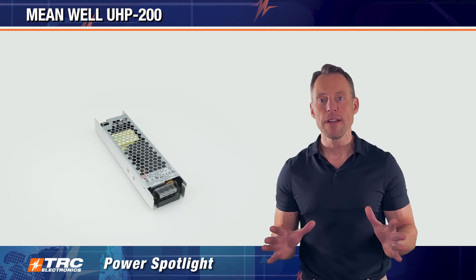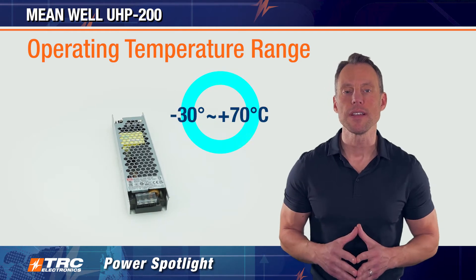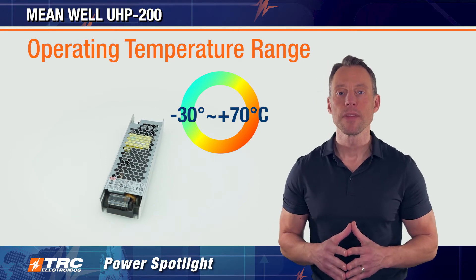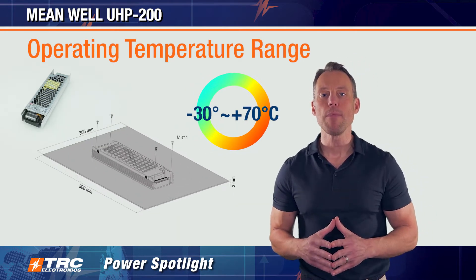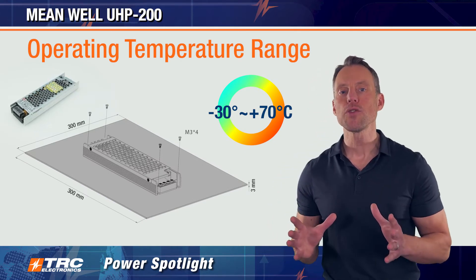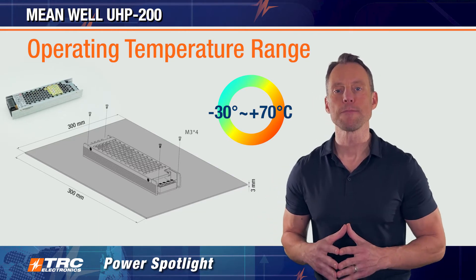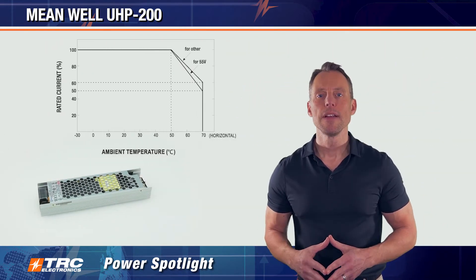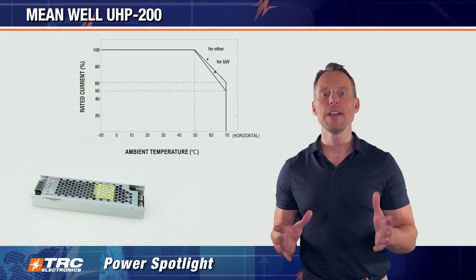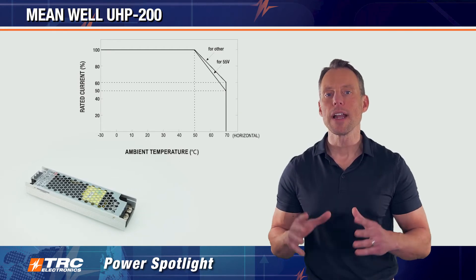This power supply has no fan, so the operating temperature range is minus 30 to plus 70 degrees Celsius. It also has base plate cooling capabilities. I'll walk you through the proper way to base plate cool this power supply using the drawing we're sharing, which illustrates the proper size of an aluminum base plate that optimizes thermal performance. The derating curve for aluminum plate cooling shows that derating begins at 50 degrees Celsius — from 50 up to 70 degrees, you won't get the full output power.